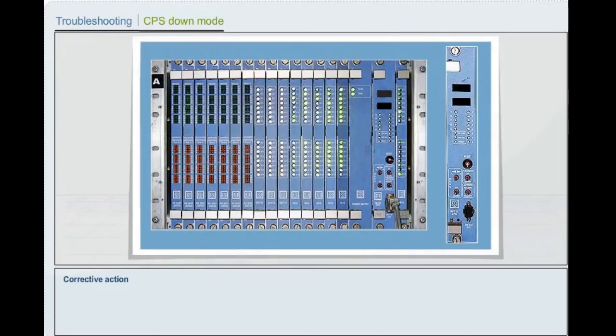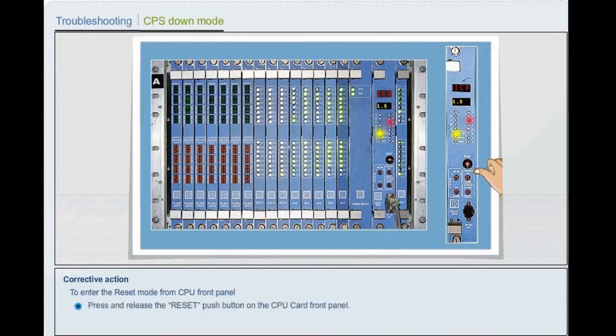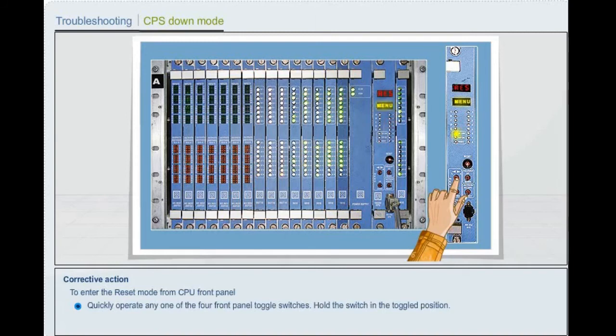Corrective action. To enter the reset mode from the central processing unit front panel, press and release the Reset push button on the central processing unit card front panel. Quickly operate any one of the 4 front panel toggle switches. Hold the switch in the toggled position.